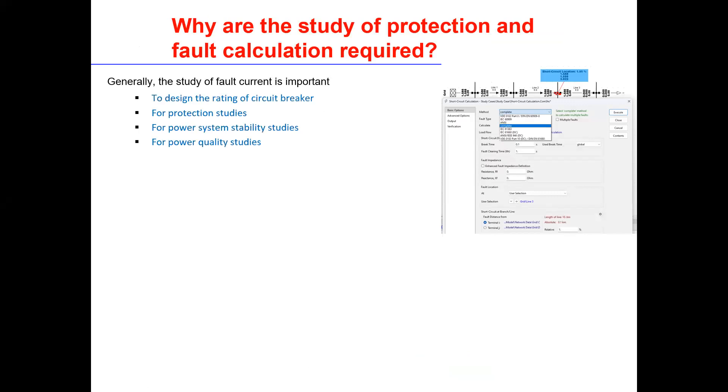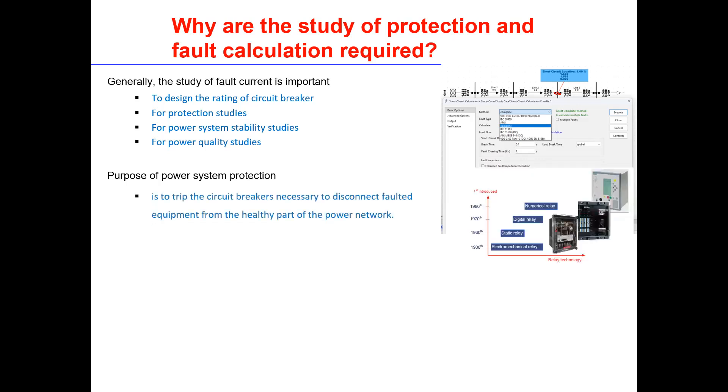The first thing we need to look at is why are the study of protection and fault calculation required. Generally, the study of fault current is important because it is helpful to design the rating of circuit breaker, for protection grading studies or coordination, for power system stability, and of course for power quality studies. The purpose of power system protection overall is to trip the circuit breaker necessary to disconnect faulted equipment from the healthy part of the power network. This is to avoid further damage to the equipment, a blackout, or cascading damage, as it is very expensive to repair the damage or the cost of damaged equipment.